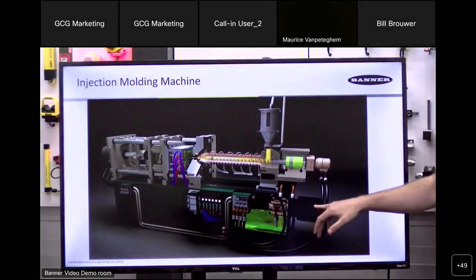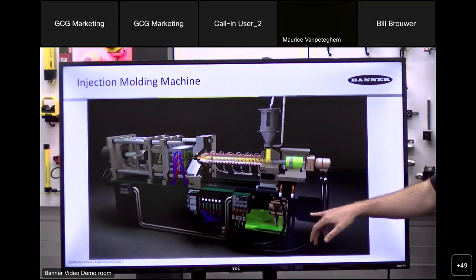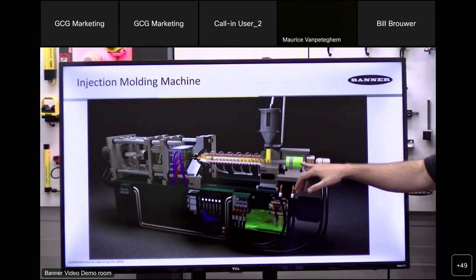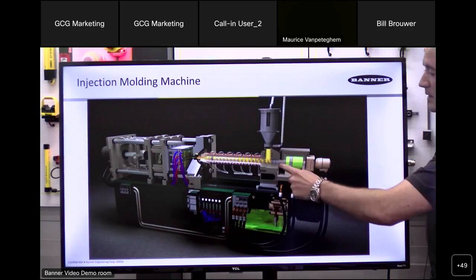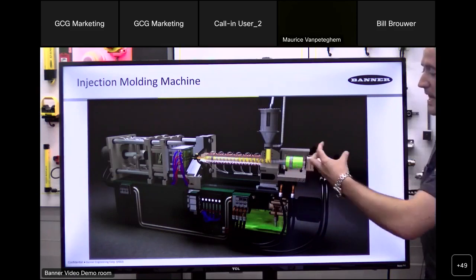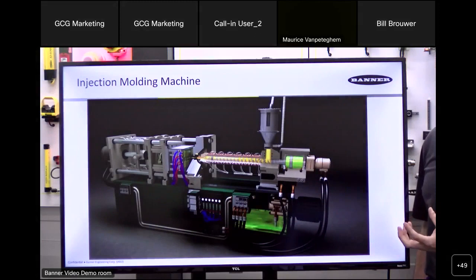Some of these pain points revolved around vibration on the motor, so being able to continuously monitor the vibration on the motor in their injection molding machines, and being able to monitor for oil leaks on their piston. What they were finding was sometimes oil would leak past the piston on their injection molding machine, and if that happened, they'd have to order a new cylinder, which could be up to a 2-week lead time - 2 weeks of downtime.